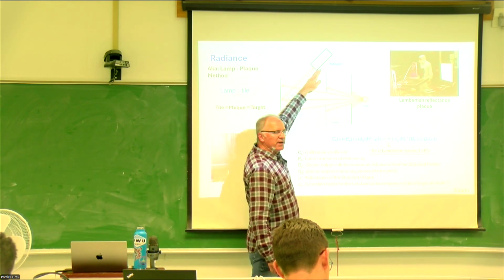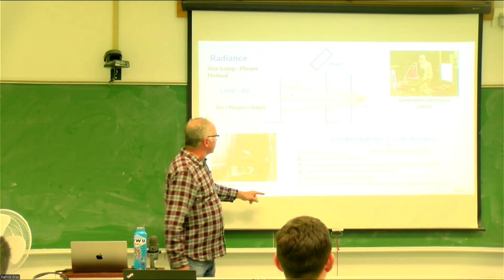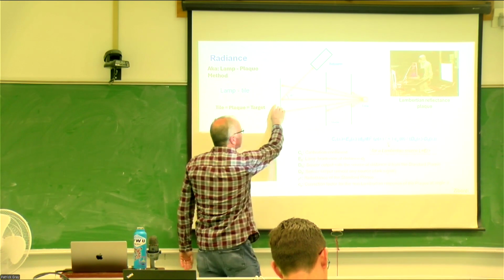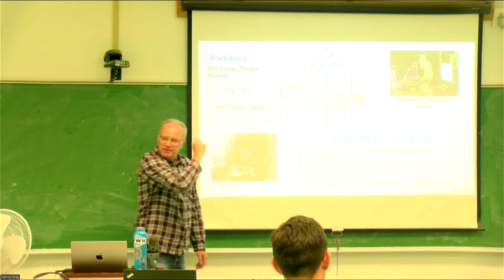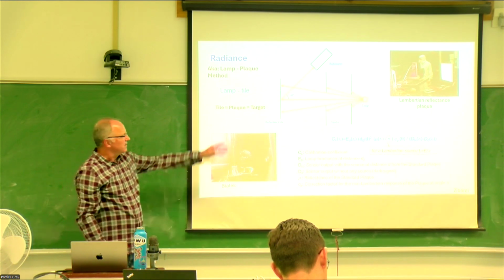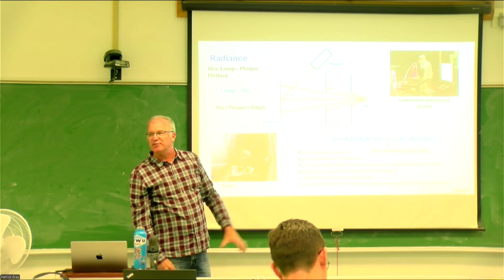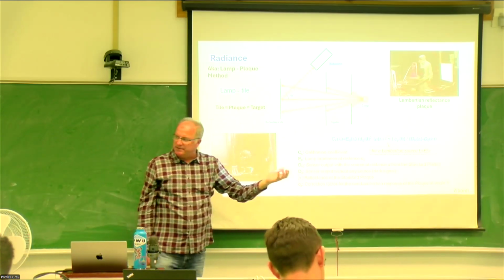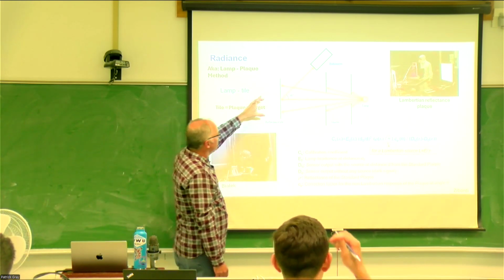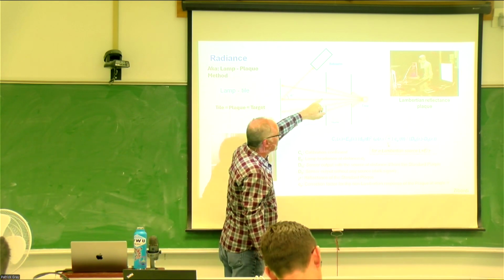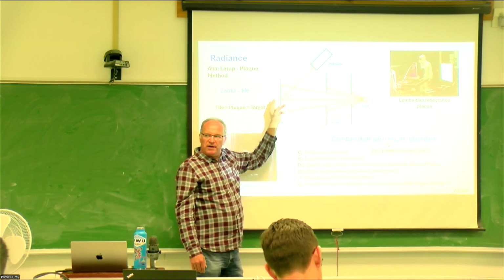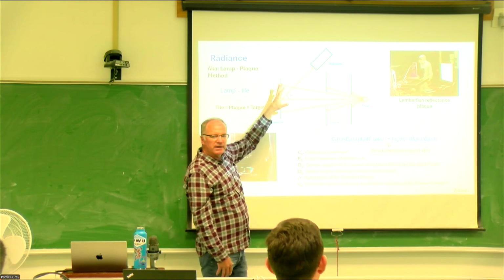You put your radiometer now at a 45 degree angle to this big plaque that's mounted here. You set another distance here, because this is again just a radiance transmission. It's a light source that emits in all directions, but radiance doesn't really change with distance. That's the principle of invariance that I talked about. But you have to make sure your illumination fills the plaque, making sure these shutters are open wide enough. Because now, like we did with the water, you've got a field of view that's staring at that plaque, and you don't want it to clip or be too big.